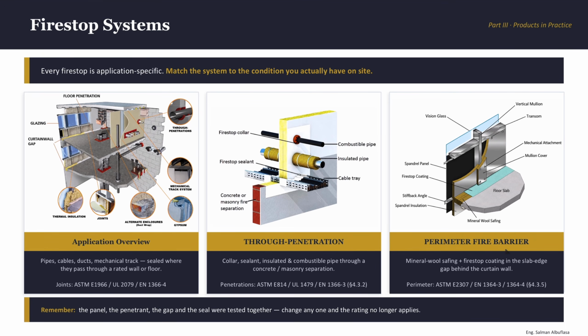And the third one is the perimeter fire barrier. This one is mostly forgotten, to be honest. This is the slab edge where the floor meets the glass curtain wall. There's always a gap there, by design, always. And fire loves that gap because it lets fire or flames spread from one floor to another, up and also to the outside of the building.